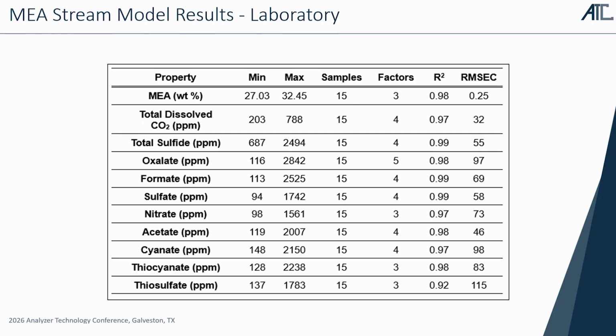And someone made a really good point yesterday that when you see these R-squared values in these modeling results for something like spectroscopy, right, they are not these like 0.9999 values that you see in things like GCs or mass specs and things like that. Really the way to view the capability of a model and the accuracy and error of it is to look at the root mean square error of the model result. So it's also really important to remember that the error is always correlated to the range, right, from the min and the max there. So being able to get down to double-digit ppm accuracy, 2 orders of magnitude less than the maximums here, is the exact sort of accuracy that our customers explain to us that they're looking for in these concentrations and samples for these heat-stabilized salts.